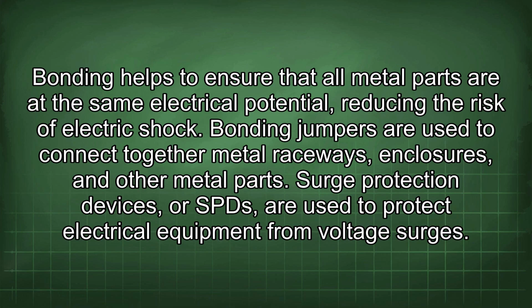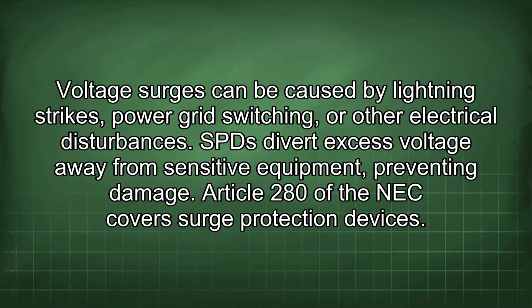Surge protection devices, or SPDs, are used to protect electrical equipment from voltage surges. Voltage surges can be caused by lightning strikes, power grid switching, or other electrical disturbances. SPDs divert excess voltage away from sensitive equipment, preventing damage. Article 280 of the NEC covers surge protection devices.